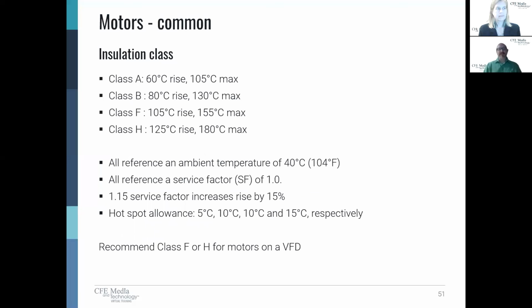And when it comes to insulation class, here we're talking about heat. Now, heat is going to be generated anytime you run current through a wire. Remember, that's part of our losses. So if I have a VFD, remember, I'm also causing spikes in voltages. I'm going to be generating a little bit more heat than I would if I didn't. So typically, when we look at classes, we're going to go with an F or an H if we're going to be running a VFD.